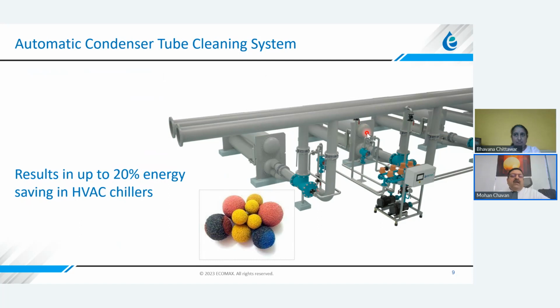It's basically an online system that helps to keep the condenser tubes clean, because when water is passing inside the condenser tubes, because of the heat transfer in the condenser and the water containing calcium and magnesium salts, there will be deposition of salts or scale inside the tubes, okay? And this system works on cleaning balls. The balls are injected and collected back, and that's how the cleaning happens with the help of these balls. And there's a potential to save up to 20% energy in HVAC water-cooled chillers by using a sponge-type condenser cleaning system.